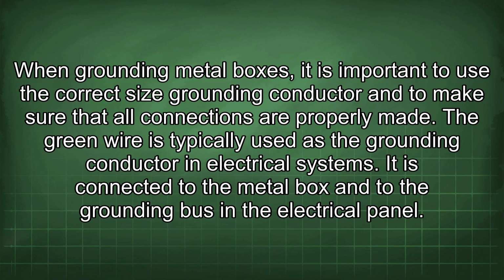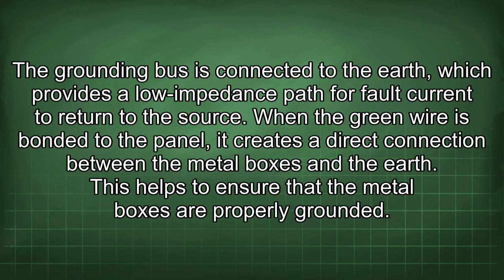When grounding metal boxes, it is important to use the correct size grounding conductor and to make sure that all connections are properly made. The green wire is typically used as the grounding conductor in electrical systems. It is connected to the metal box and to the grounding bus in the electrical panel. The grounding bus is connected to the earth, which provides a low impedance path for fault current to return to the source. When the green wire is bonded to the panel, it creates a direct connection between the metal boxes and the earth. This helps to ensure that the metal boxes are properly grounded.